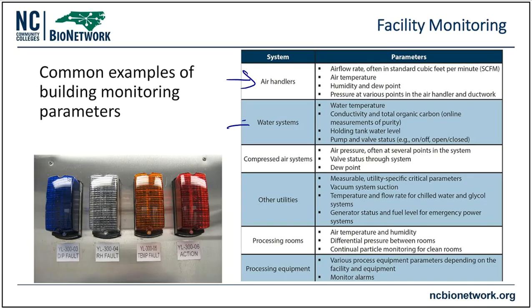Water systems, of course, have to be monitored -- we've talked about this over and over. The temperature of the water, the conductivity, the TOC content -- how dirty or clean is it? Levels of holding tanks -- for water for injection, what are the fill levels, do we need to add more or drain some out? All of this falls under the building inspections and monitoring that must take place daily.